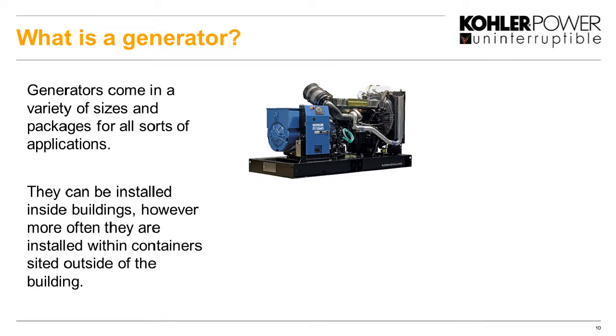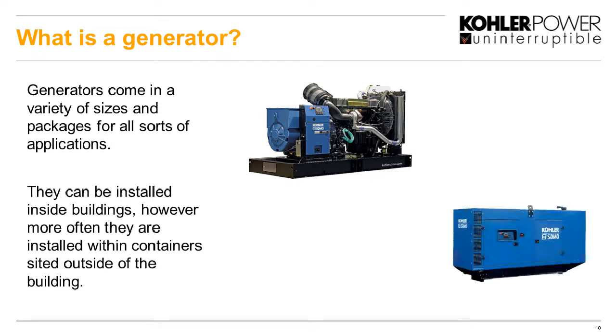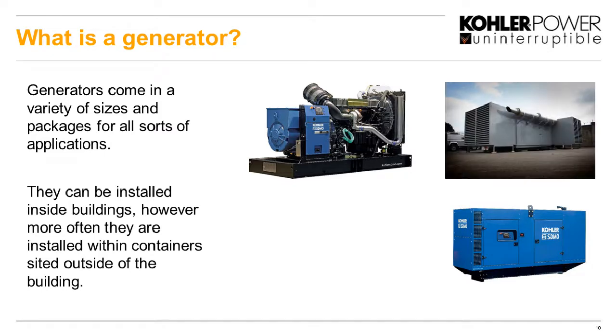Okay. So generators do come in all variety of sizes and packages. They can be installed inside buildings. However, very often they will be installed inside a self-contained container here, as you can see bottom right. Okay, so that is a typical thing. We move that along, put it outside the building, and that will be self-contained, and we cable that in and out from that point. Okay, but we also have some installations, containerized, but they're so large that they actually have to be put together on site. And we can see that on the top right, where that comes in modules, and it's built up on site as well.